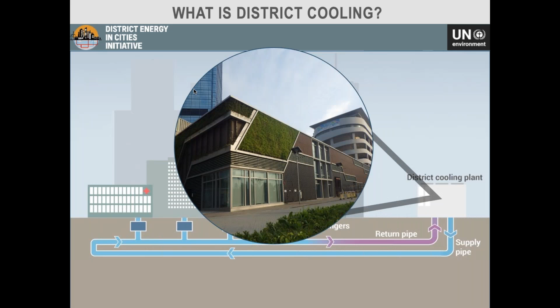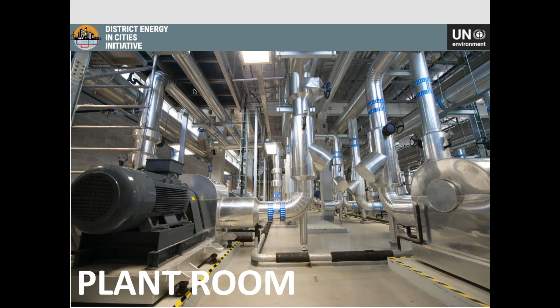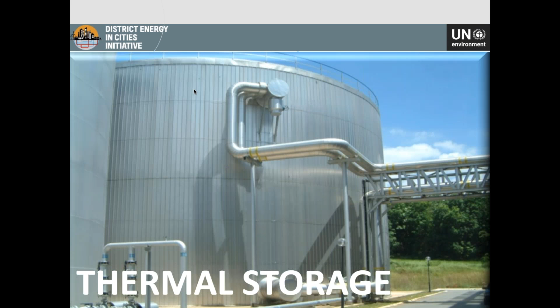This will have a control room and a plant room, where you've got chillers and pumps producing very cold water around 4 to 5 degrees Celsius. This is managed from the control center, where they dispatch this chilled water to the buildings. In that plant room, you can also have thermal storage where we chill water at night and release it during the day, so we don't have to use electricity during peak periods.